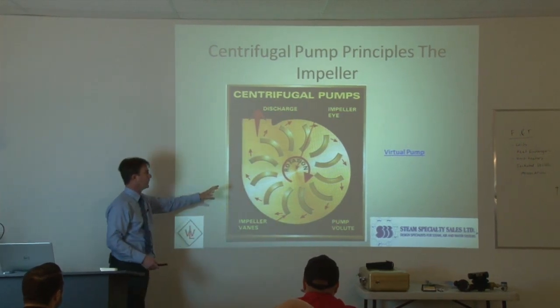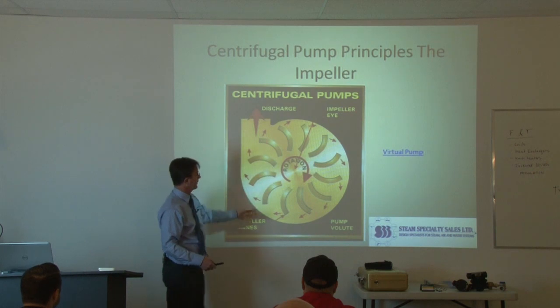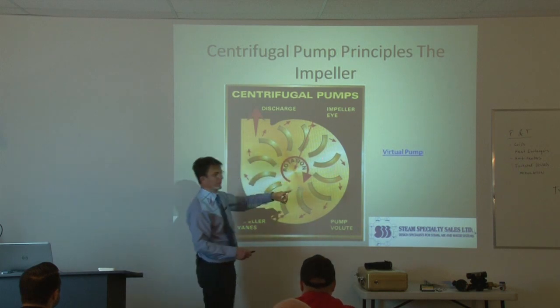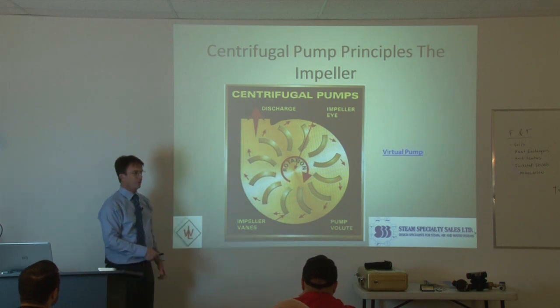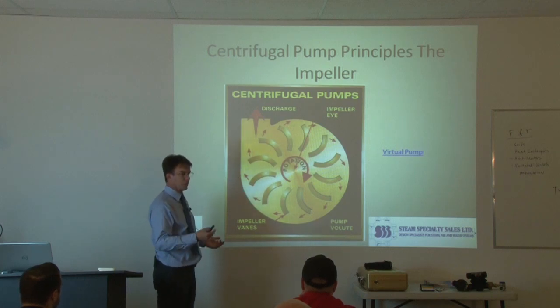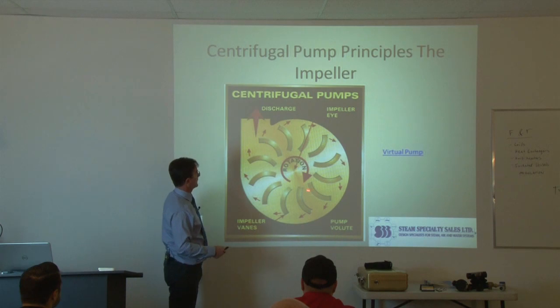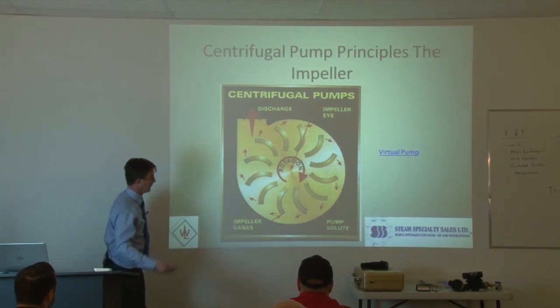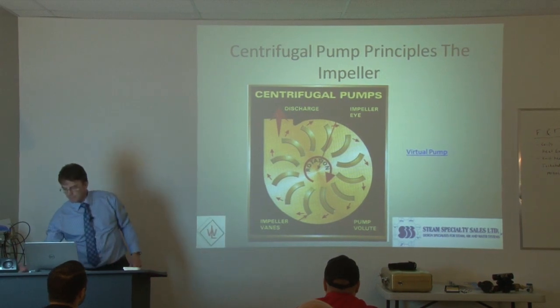Never put a strainer upstream of a centrifugal pump - this is straight from Shipco's installation and operating manuals. With a vane-type centrifugal pump, the vanes are very far apart; you could probably fit an entire finger inside the vanes. Having a strainer upstream is an extra maintenance point that doesn't get checked enough, so the strainer can get plugged and cause the pump to fail. With a centrifugal pump, water comes in through the center - the eye of the impeller - and gets slung around. It's the opposite of a propeller: the impeller draws water in, while a propeller pushes the boat away.